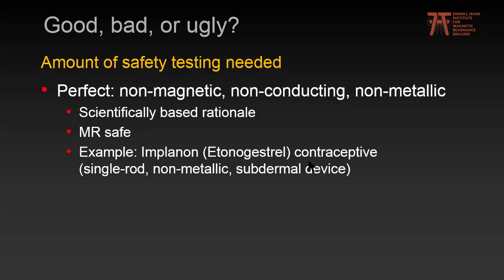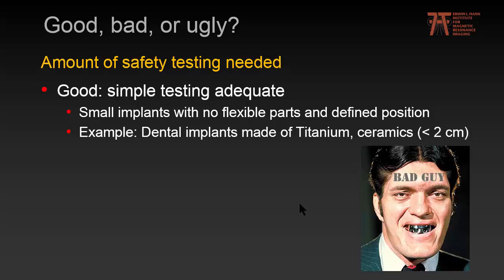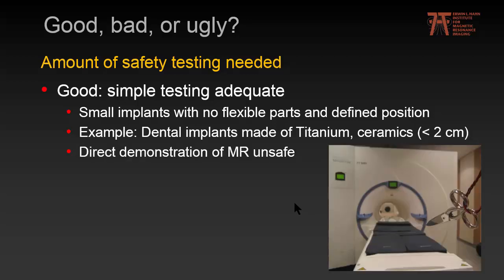An example of a perfect implant is the implant contraceptive, which is a single rod, non-metallic, sub-dermal device. Good implants require only simple testing — typically small implants with no flexible parts at a very defined position, such as dental implants. Note that if there is too much dental work, this can also turn bad. Also, if you can directly demonstrate that an item is MR-unsafe, you are done with your safety assessment immediately — just one demonstration of MR-unsafe is enough, whereas just one example of MR-conditional may not be.